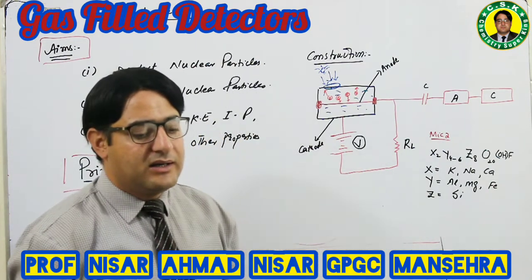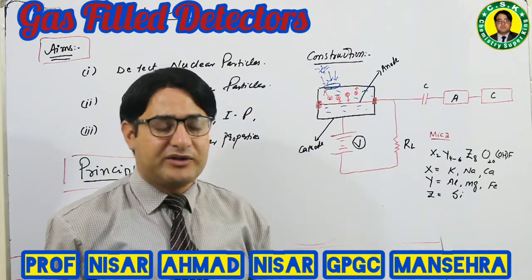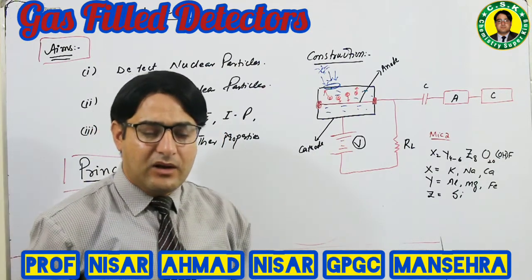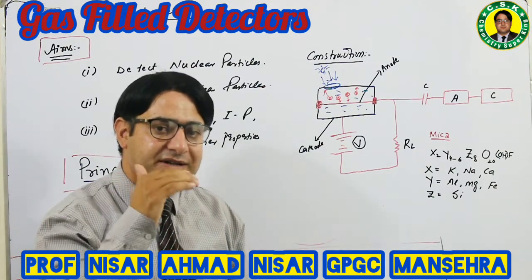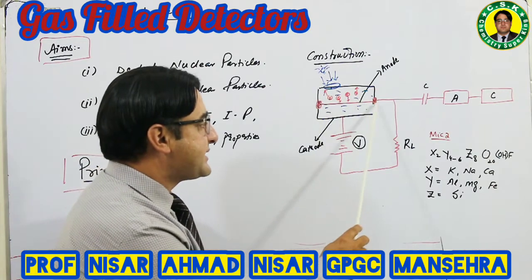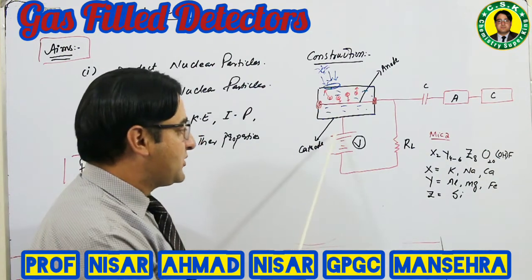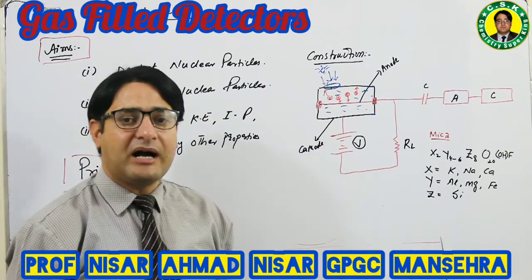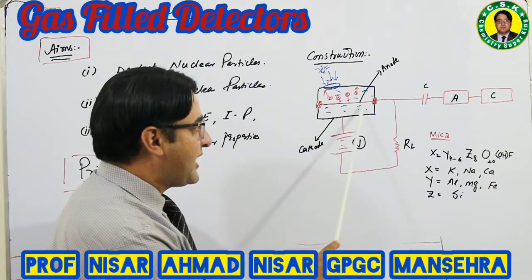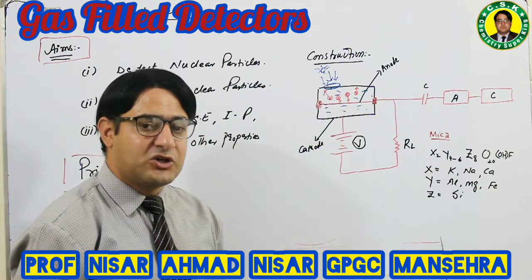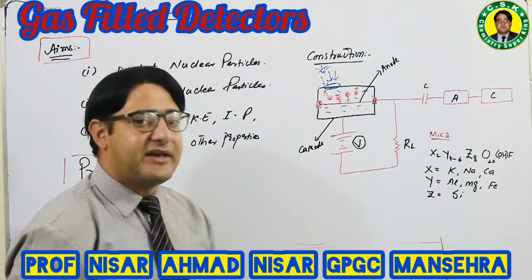Now for construction — a typical gas ionization detector as shown in the figure has a hollow metallic cylinder connected to the negative terminal of the battery, acting as a cathode. Inside the center there is a wire, usually made of tungsten, connected to the positive terminal of the battery, acting as an anode.